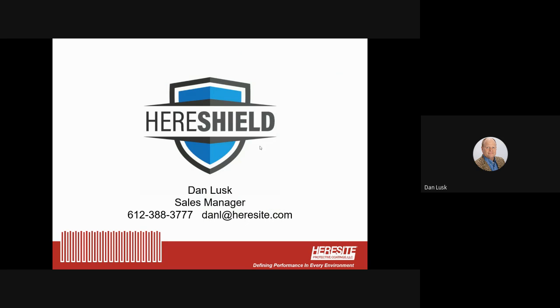What's the latest on coating aluminum microchannel coils, and are there best practices or best products from Heresite? You can use the products that I talked about here. It's important to note there are some inherent issues with coating MCHX coils. First of all, it's hard to get the atomized paint you're spraying into the center of the coil. If you have more than 2 or 3 rows, it's going to be difficult to get that paint into the center because the openings are really small. The other thing we found is the natural design of that coil makes it more conducive to corrosion, holding corrosion, chemicals, and salt air more than a fin tube coil.